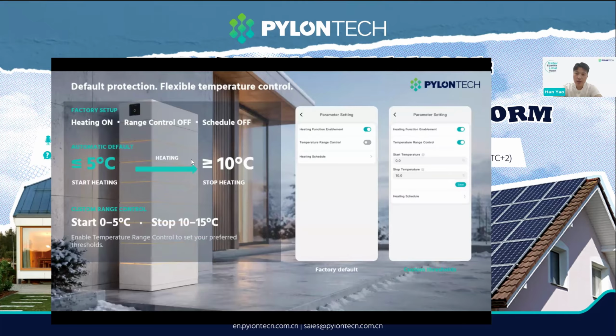Let us make the heating logic very simple. For the factory, heating is on, while custom temperature control and the schedule are off. In the default mode, heating starts when the battery temperature reaches 5 degrees Celsius or below. It stops when the temperature reaches 10 degrees. If the user enables temperature range control, the start point can be set from 0 to 5 degrees, and the stop point from 10 to 15 degrees. So the system is protected from day one, but the user still has flexibility when the project needs it.